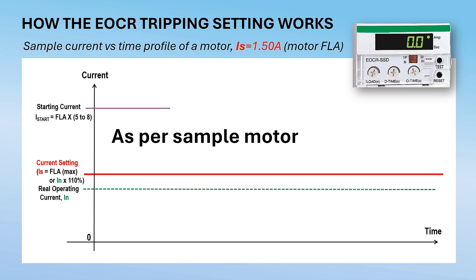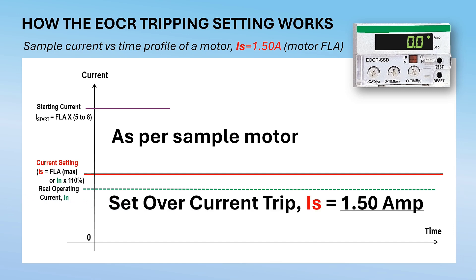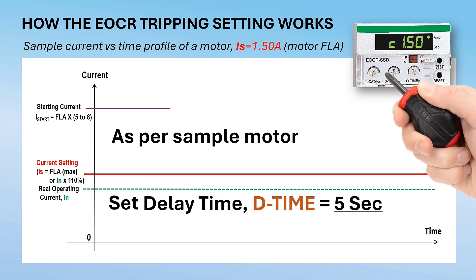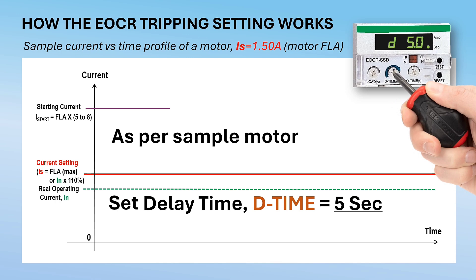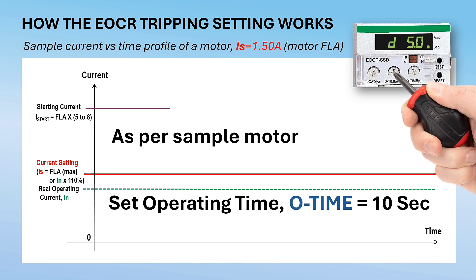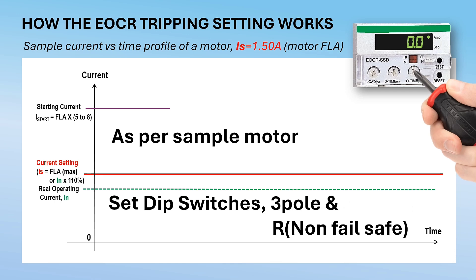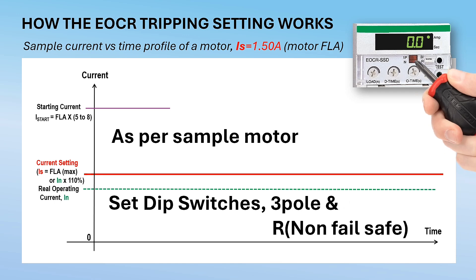After collecting the information about the motor FLA, we can now set the parameters in the EOCR. Set the overcurrent trip by turning the load setting knob clockwise until reaching the desired set value — the display will show an increment of 0.10 ampere for each step. Next, set the delay time or D-time to five seconds. Next, set the operating time or O-time to 10 seconds. Then set the dip switch as per your system requirements for single-phase or three-phase, and fail-safe or non-fail-safe as per your application.